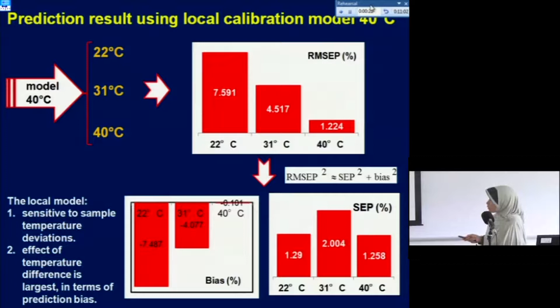Then using the local calibration model at 31 degrees Celsius, we obtain good prediction for samples at the same temperature, but worse prediction for samples at a different temperature. Also, the effect of temperature difference is larger in terms of bias, not SEP. The same result was observed for the local calibration at 40 degrees Celsius: we obtain good prediction for samples at the same temperature and worse prediction for samples at a different temperature. Again, the effect of temperature difference is larger in terms of bias, not SEP.